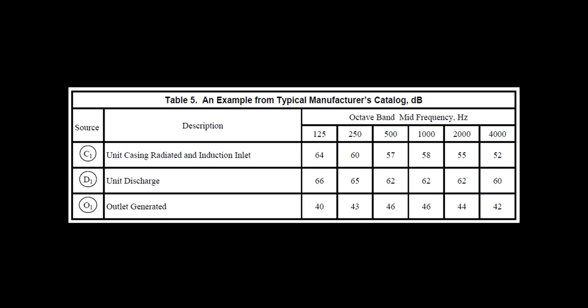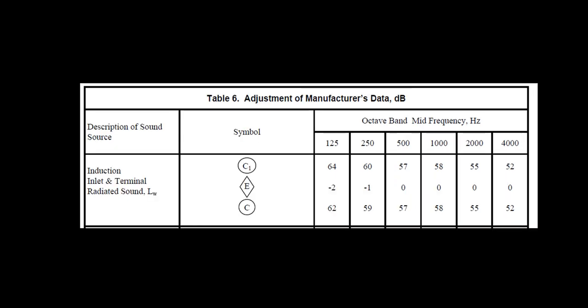Now let's start by looking at all of the attenuation that is present for each of the paths. Since path 1 has the least amount of variables, let's start there. One common attenuation is the environmental adjustment factor. While in indoor areas, rooms tend to be highly reverberant, which leads to less radiation of low frequency bands. We must adjust our source sound to accommodate this. This is a 2 dB reduction in the 125 Hz band and a single dB in the 250 Hz band.